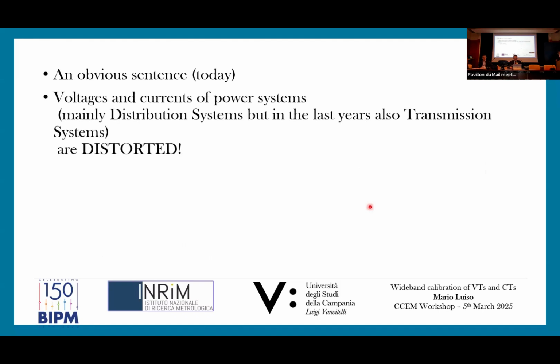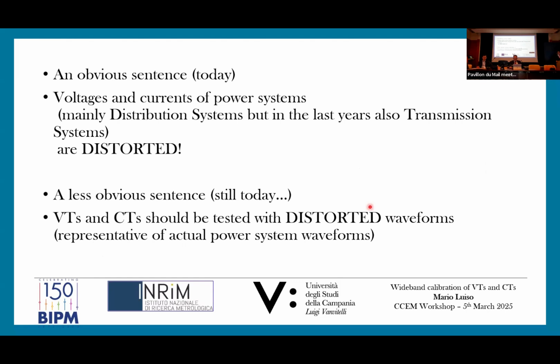An obvious sentence for today is: voltages and currents of power systems are distorted. But a less obvious sentence still today is: VTs and CTs should be tested with distorted waveforms. Distorted waveforms in the sense that they should be representative of actual power system waveforms.